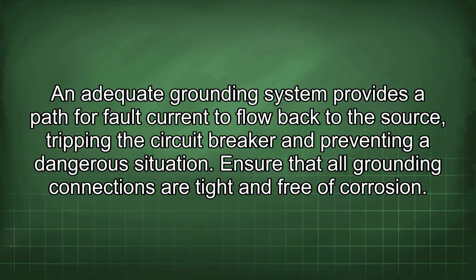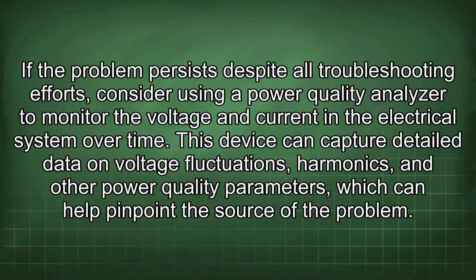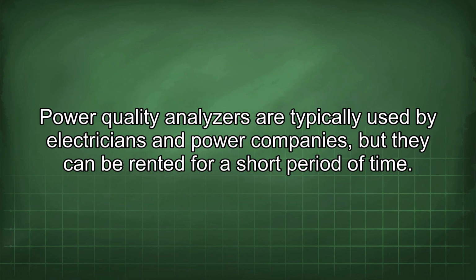Ensure that all grounding connections are tight and free of corrosion. If the problem persists despite all troubleshooting efforts, consider using a power quality analyzer to monitor the voltage and current in the electrical system over time. This device can capture detailed data on voltage fluctuations, harmonics, and other power quality parameters, which can help pinpoint the source of the problem. Power quality analyzers are typically used by electricians and power companies, but they can be rented for a short period of time.